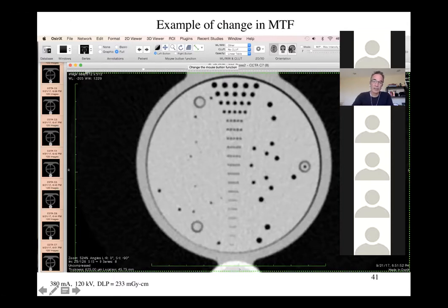So out here, if an X-ray comes through and doesn't hit this object at all, and it hits our detector, which is down here, we're going to see a large number of X-rays hitting the detector there. So that function shows very high values where you have little absorption, and low values where you have high absorption. We'll see that function is transformed such that the polarity is flipped, and you get a negative of the scan.